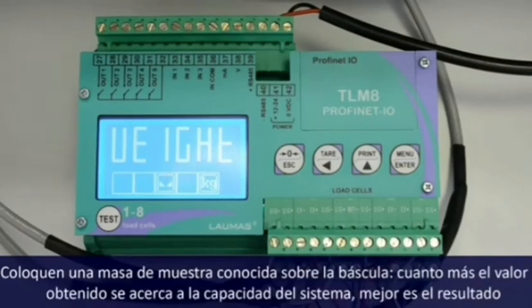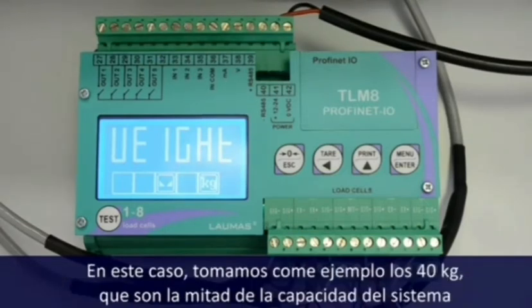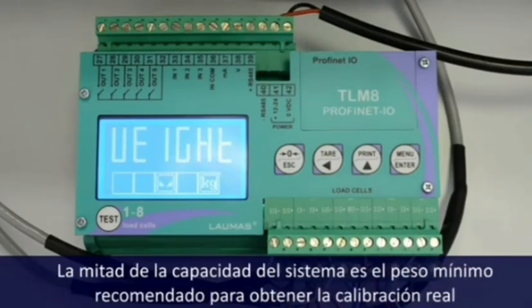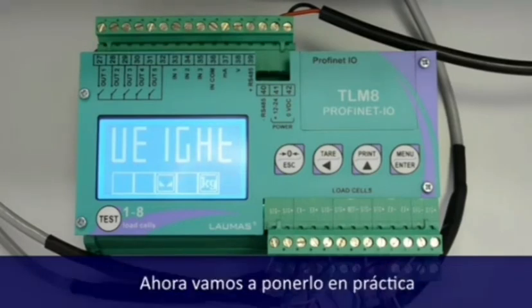Put a known sample mass on the scale. The closer the value to the system's capacity, the better. In this case, I will use 40 kilograms, which is 1/2 of the system's capacity. 1/2 of the system capacity is the minimum weight we recommend for real calibration. Let's do it.